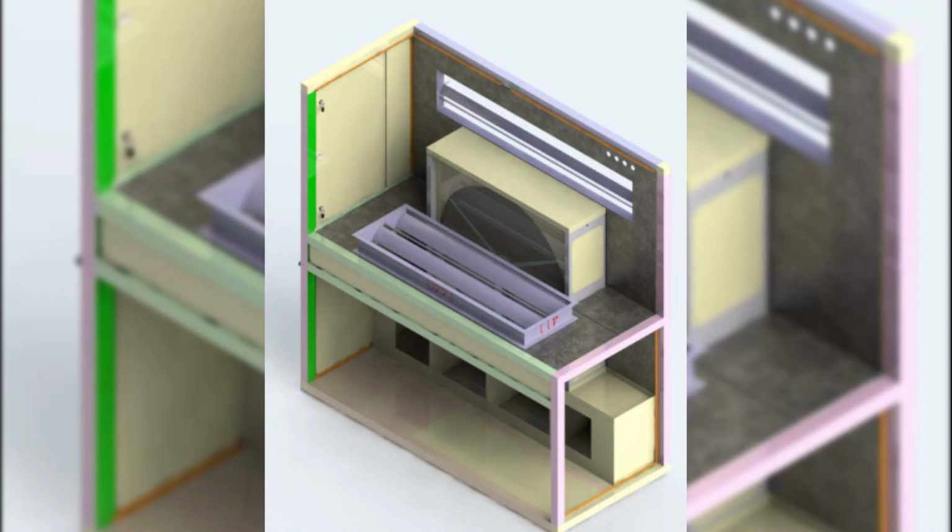The purpose of an ERW is to recover energy from exhaust air, which helps to reduce the heating and cooling loads on the HVAC system. DCV system adjusts the amount of outside air delivered to a space based on the actual occupancy, typically by using CO2 sensors. By reducing the amount of outside air when the space is not fully occupied, DCV systems save significant energy.